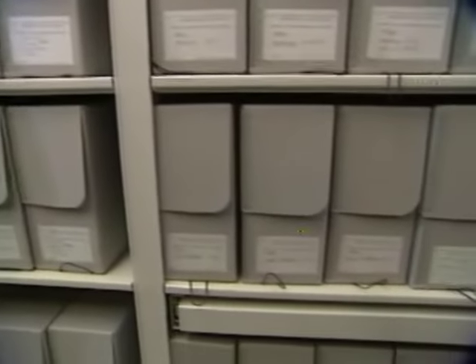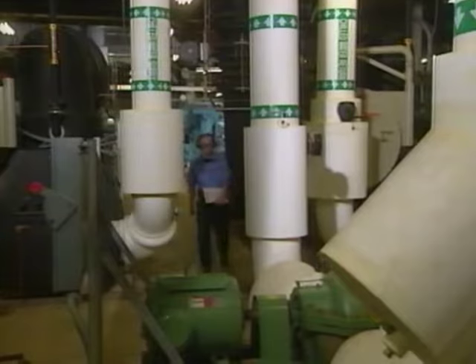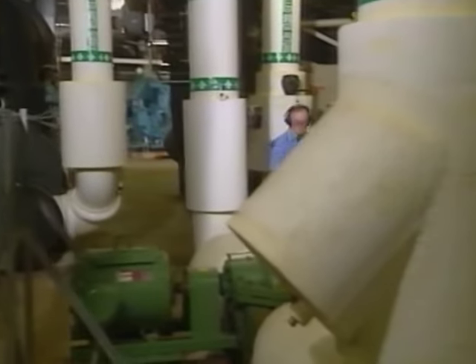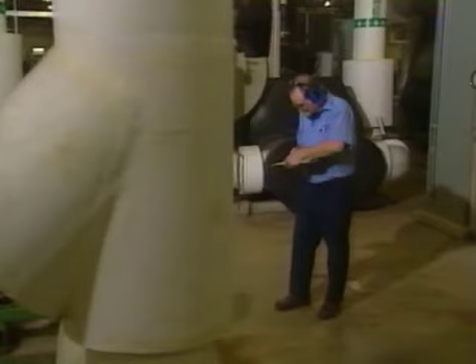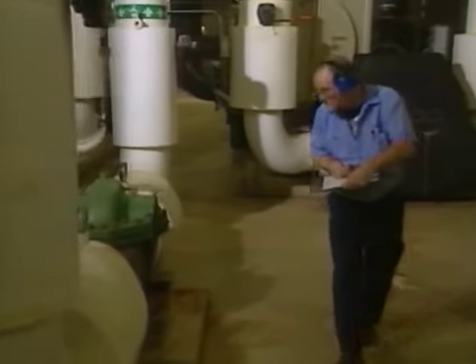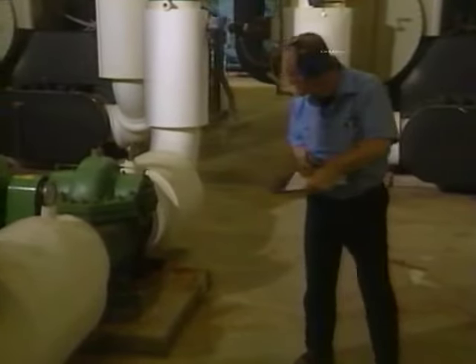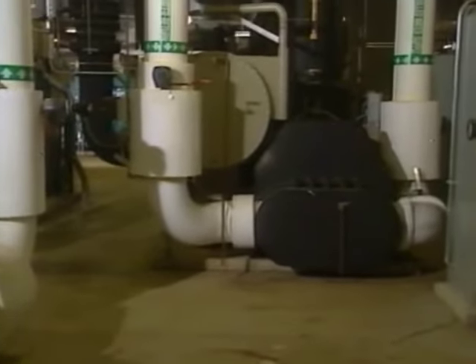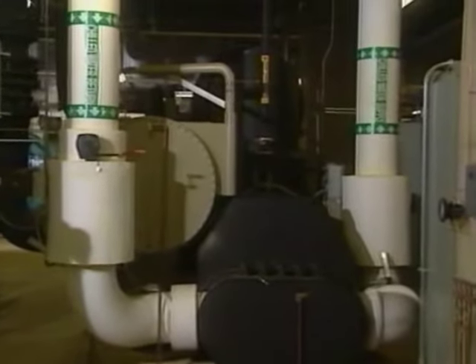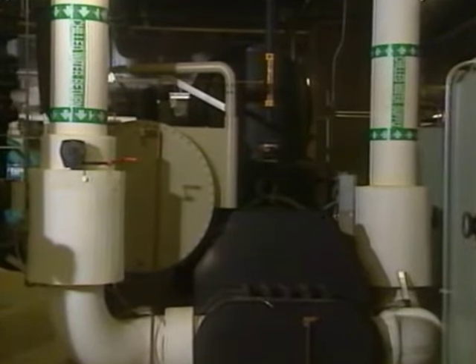From a preservation standpoint, the two most damaging elements to the preservation of documents relate to the stability of temperature and relative humidity and the removal of gaseous and particulate pollutants. There are four main water-cooled chillers located in the central plant which generate chilled water for air conditioning in the stack areas. The chilled water is fed through cooling coils in each of the air handling units feeding the stack areas in order to achieve the required temperature within the stack area.